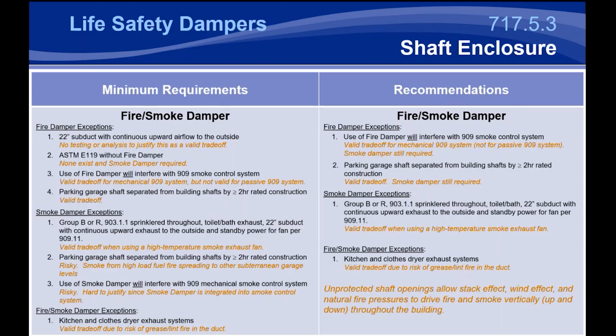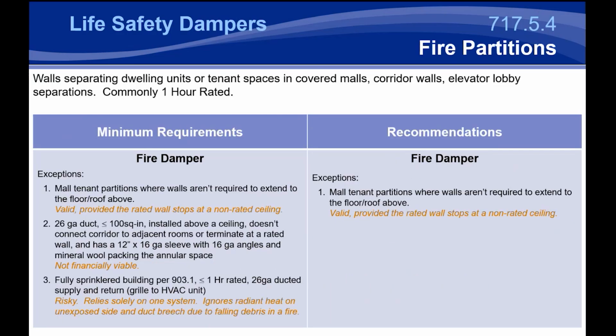So we definitely recommend removing those for kitchen and clothes dryer exhaust, or say if you've got bathroom exhaust ventilation. Now that is the smoke damper and the fire damper exception. There are some additional exceptions that tie into this down through the rest of this presentation. Now, for fire partitions, you're probably going to see these mostly in corridor walls.